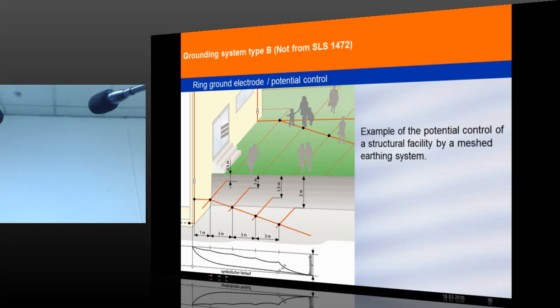So you have to go through those standards, and soil equipotentialization is also required. Soil equipotentialization is nothing but a simple way of making equipotentialization of the soil around the building where people movement is more, or where you need protection against step contact. So here the method is, you see, there is a ring conductor. The first one is 1 meter away from the building and a half meter below. The second ring conductor is 3 meters away from the first one, but 1 meter below. Again 3 meter, half meter more down. Again 3 meter, half meter down. So this way of making soil equipotentialization will protect people outside the building.